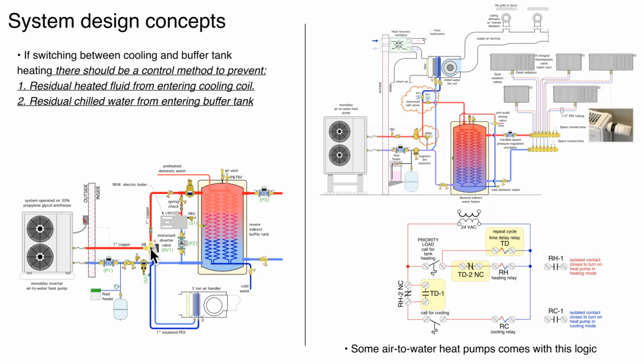And the same thing occurs when we're going from cooling into domestic water heating. We have cool fluid in this piping. This valve would be shut. The heat pump would operate in heating. It would rapidly heat the fluid here. Then this valve would open and the fluid would go over to the buffer tank. I put together some relay logic. A time delay relay is making the decision on when this can happen. You could also use temperature sensing to make the decision.